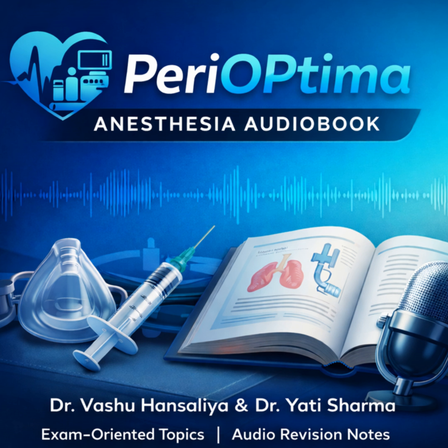So how does the Tec 6 vaporizer handle it? It's a completely different technology. It doesn't use variable bypass at all. It heats the Desflurane liquid to 39 degrees Celsius, creating a pressurized gas at 2 atmospheres. It then injects this pure Desflurane vapor directly into the fresh gas flow using a differential pressure transducer. It's an injector or a blender, not a traditional vaporizer.